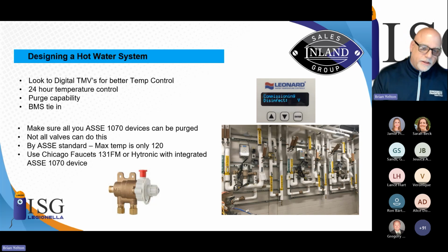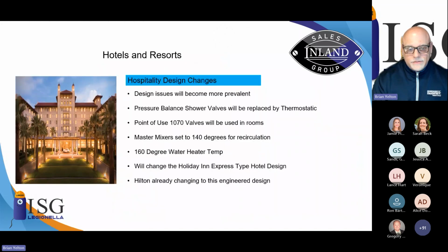Make sure your ASSE 1070 devices can be purged. That means we can run 160, 170, even 180 degrees through them if we're monitoring them to clean them. A standard ASSE 1070 device cannot do that, it's going to tap out at 120. So look at products like the Chicago Faucets 131FM, a great key.